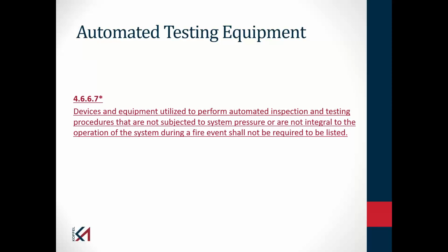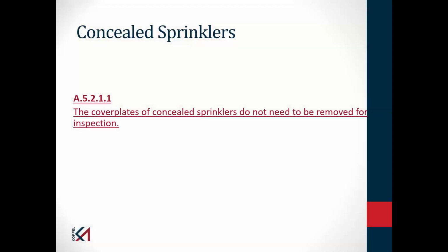So again, you're going to see increased recognition for automated test equipment. We're not quite there for fire pumps. You still have to flow 150% of the rated capacity of the pump, but I would hope that at some point in time, technology may get us there.